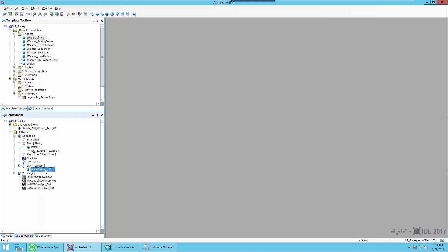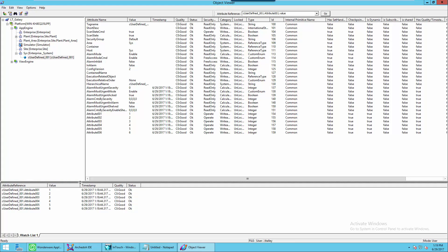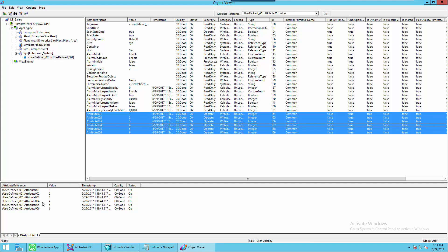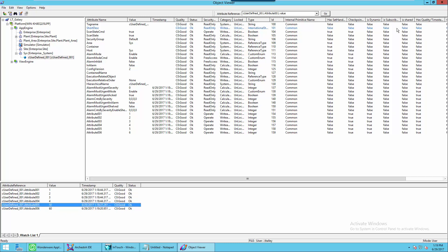Now we'll go ahead and deploy the object. We added all the values to the watch window in Object Viewer just to see the values, and I'm going to change one. I'm going to change attribute six to 60 and attribute five to 50. This might be useful if you want to change alarm set points in runtime, but not necessarily upload runtime changes, which affects all the attributes on the object, as well as the default value.